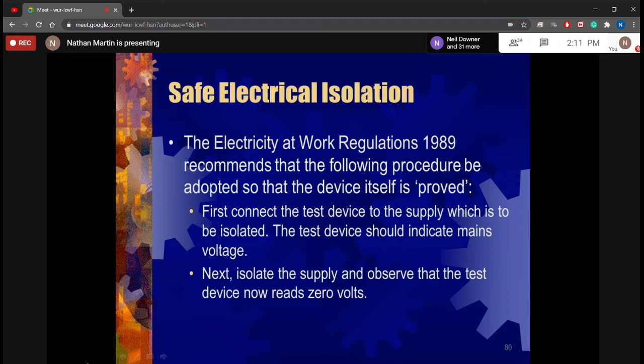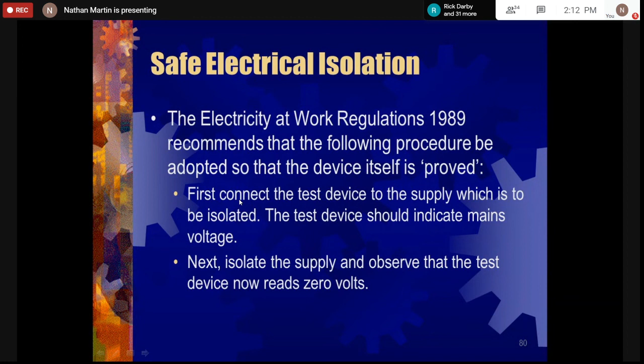There are certain procedures that you must follow, but we don't follow them in Jamaica, or in a lot of countries, but I must teach it to you because this is how it starts. The Electricity at Work regulation recommends that you first connect the test device to the supply, to a known supply that you want to isolate, test the device again on the mains - like say a panel, make sure your device will work, identify the circuit that you need to isolate, test, isolate the circuit, test that the circuit is dead, and then retest your meter on the mains again.